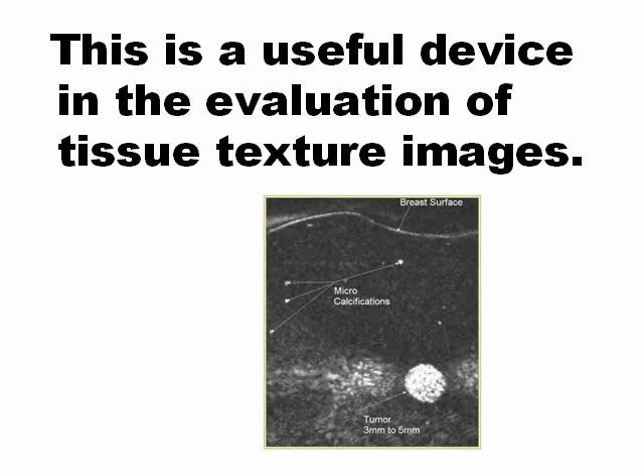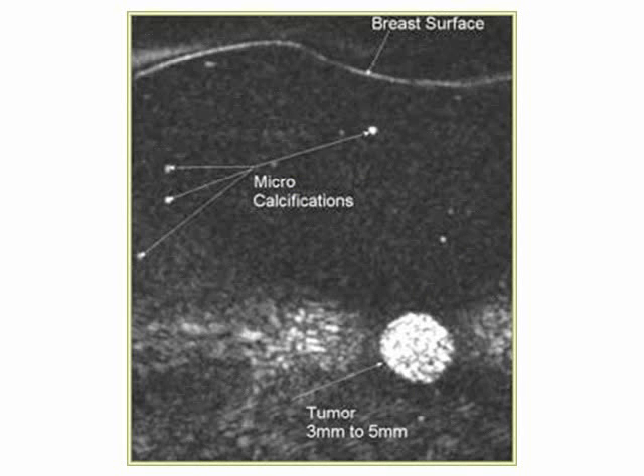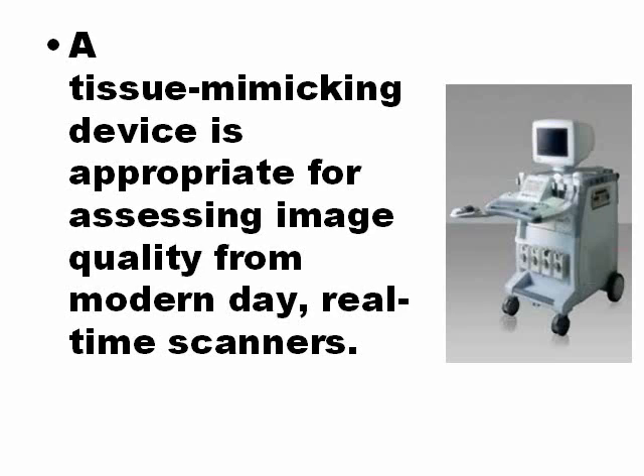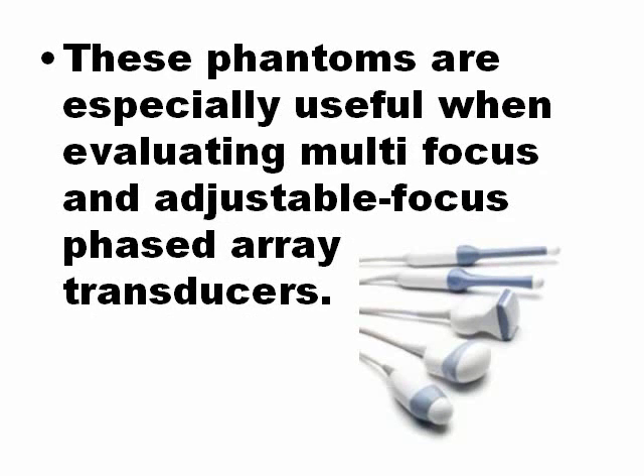This is a useful device in the evaluation of tissue texture in the image. There is one picture here with a tumor, with microcalcification, with the breast surface. This is a phantom to help in the breast examination. You can see here that there are structures that mimic the structures that we can find in breast ultrasound. A tissue mimic device is appropriate for assessing image quality for modern-day real-time scanners. These phantoms are very good for evaluating multifocal and phased array transducers.